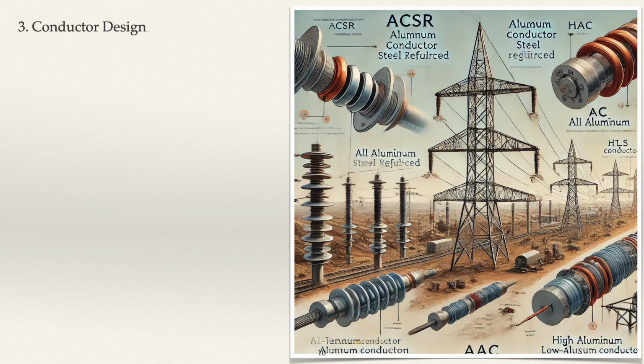6. Corrosion resistance. Conductors are often exposed to harsh environmental conditions, including moisture, salt in coastal areas, and pollution. Protective coatings or materials with corrosion resistance, like galvanized steel or aluminum alloy, are often used. 7. Thermal expansion. Conductors expand and contract with temperature changes, which affect sag and tension. Proper design accounts for these variations to ensure safe operation under all weather conditions.